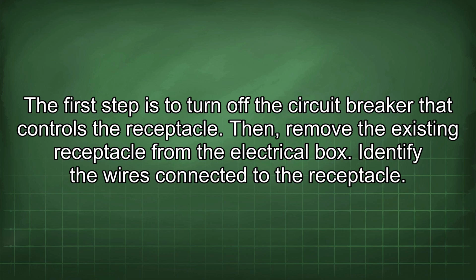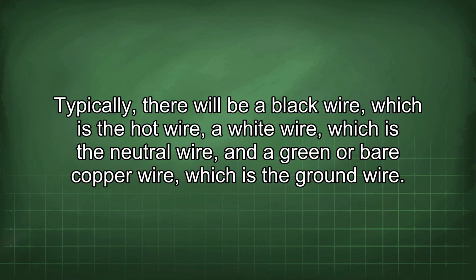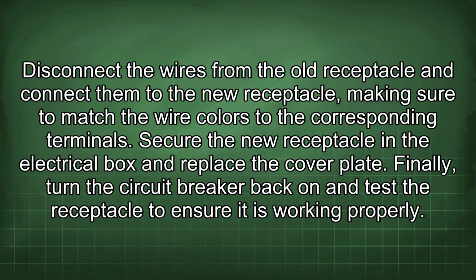Identify the wires connected to the receptacle. Typically, there will be a black wire, which is the hot wire, a white wire, which is the neutral wire, and a green or bare copper wire, which is the ground wire. Disconnect the wires from the old receptacle and connect them to the new receptacle, making sure to match the wire colors to the corresponding terminals. Secure the new receptacle in the electrical box and replace the cover plate. Finally, turn the circuit breaker back on and test the receptacle to ensure it is working properly.